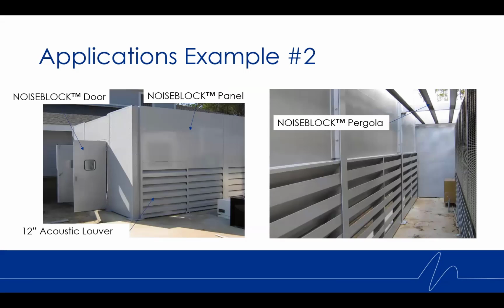Here you can see on the outside, we've used our noise block panel to make an enclosure around it. We've included our acoustic louvers as a bit of a skirt there to allow for the airflow. And then we have an access door to make sure that someone can go in and do regular maintenance on the equipment. The picture on the right there, you can see on top, we've used our same noise block panels, but essentially made a pergola roof. So for the same reason as the louvers, we are just allowing for proper airflow, but then trying to mitigate that noise that's being emitted upwards from the chiller.